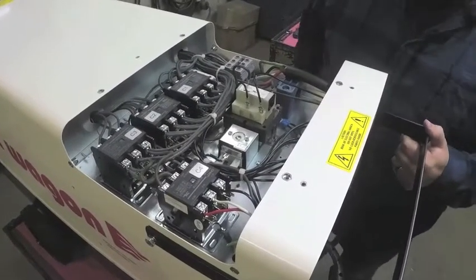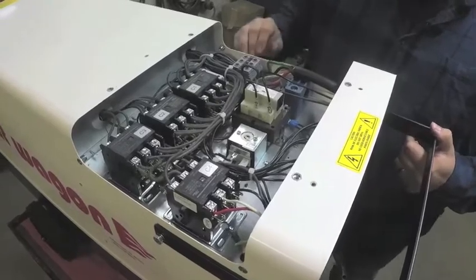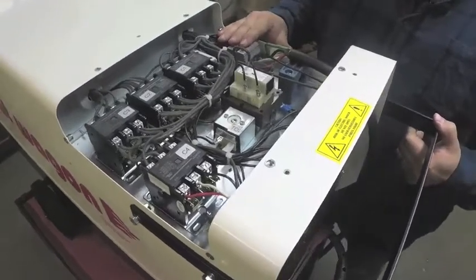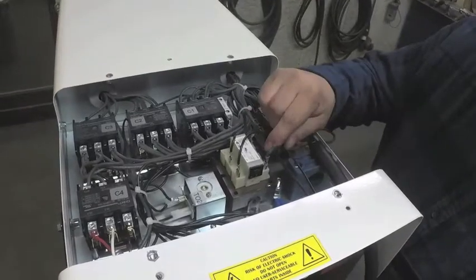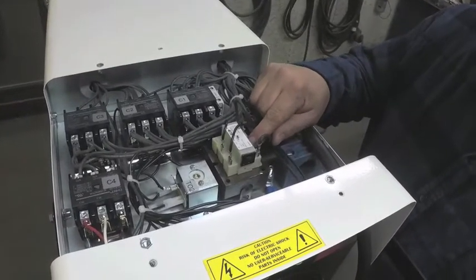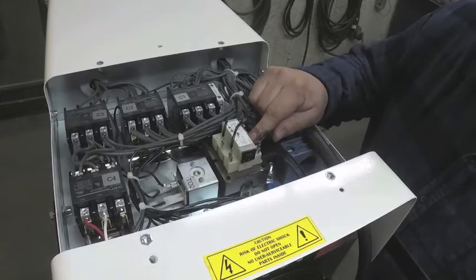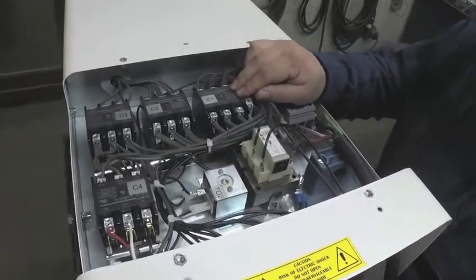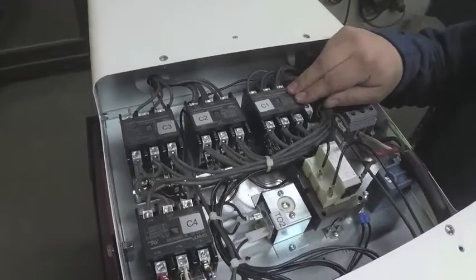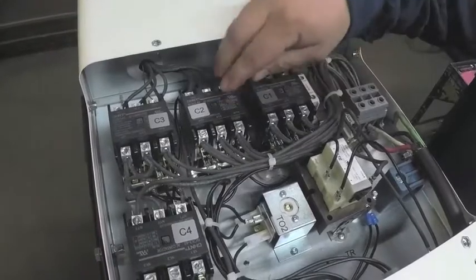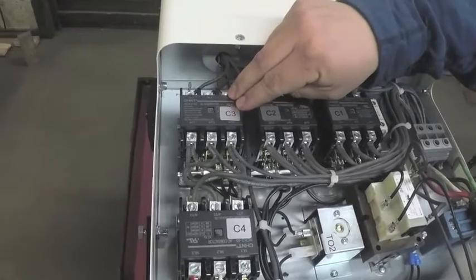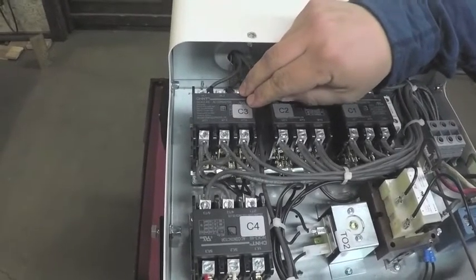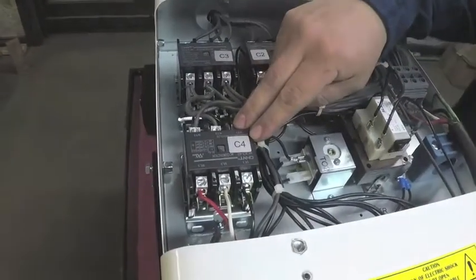Next, we're going to be talking about internal components under the hood. This is your input power terminal block. This is your 480 three phase to 24 volt AC transformer. This is your C1 relay, your first stage heating relay. C2 relay is your second stage heating relay. C3 is your third stage heating relay and C4 is your fan relay.